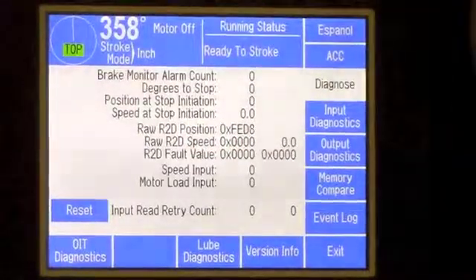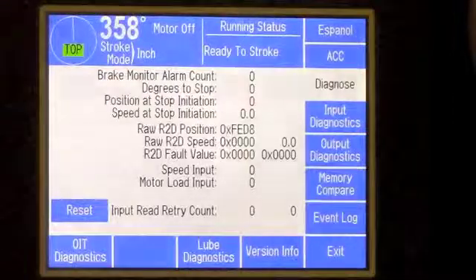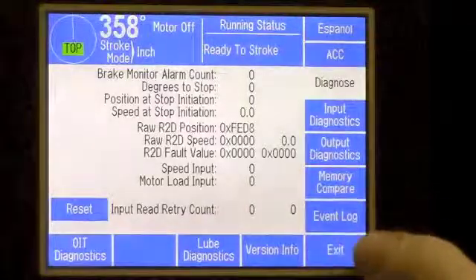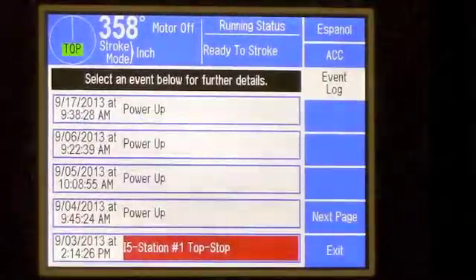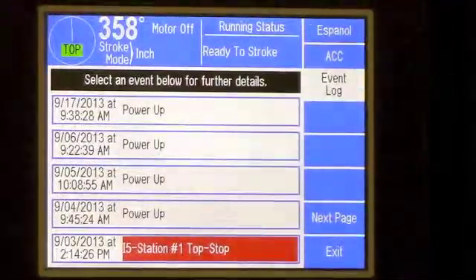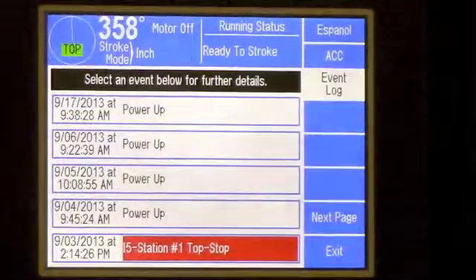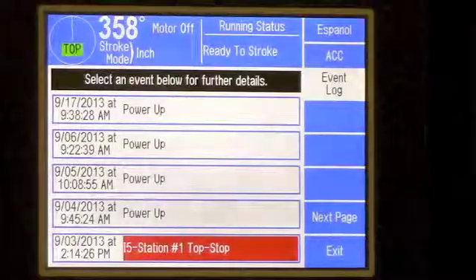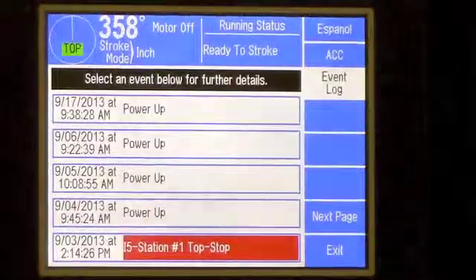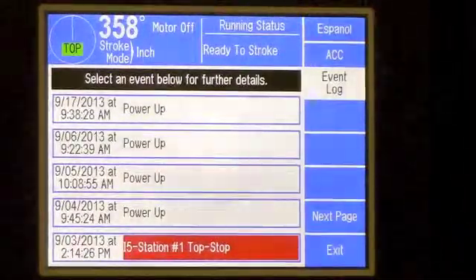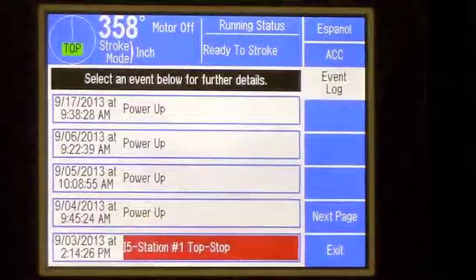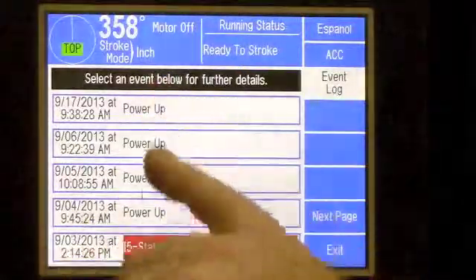Another good feature in the diagnostics menu is the event log. From the diagnostics menu, press the touch button on the right hand side for event log. Once that is pressed, it shows every fault or any condition that would have caused the press to stop — whether it be a tonnage monitor fault, a counter, a pressure switch, anything tied into the press control that caused the press to stop is going to be registered on this log. It cannot be erased or changed other than putting in a new press control. This is very helpful, especially for troubleshooting, to see if you are getting repeated faults.